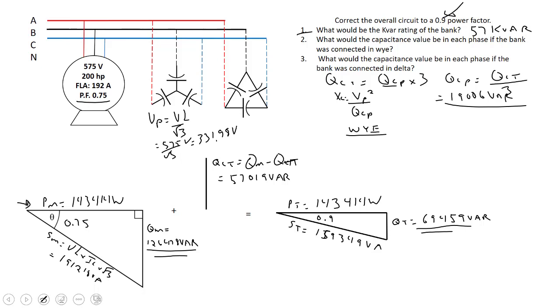Let's use our formula now. So XC equals 331.98 volts squared divided by our reactive power per phase from our capacitor bank, 19,006 VAR. That works out to be about 5.8 ohms.